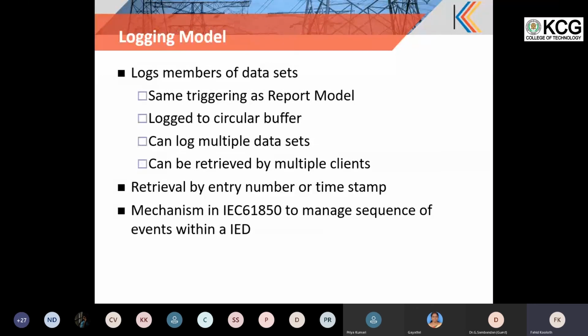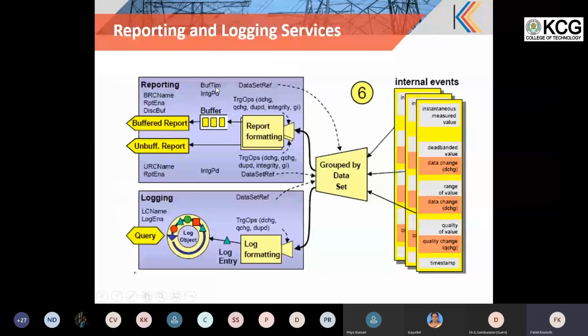So you have grouped data, grouped by the data set. Now this is associated with a report control or log control block. And you can define the trigger options that need to trigger this report, like data change, quality change, data update, integrity, or general interrogation. And there are two types of report: unbuffered report and buffered report. For unbuffered report, there is no buffer. So whenever there is a change in any of the data associated with the data set, this report is sent out.